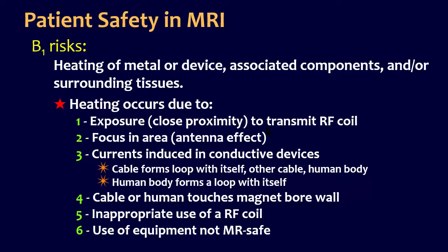This cable or human that touches the bore wall, and somehow there is a current induced. The always popular inappropriate use of an RF coil. I work in a research institution, so I'm constantly working with my students on how not to put the cardiac coil inside the head coil, because it's really not going to work all that well, and it's dangerous. Another one that we see quite a bit in clinical facilities is the use of MR monitoring equipment in the magnet room with the patient that is not safe.